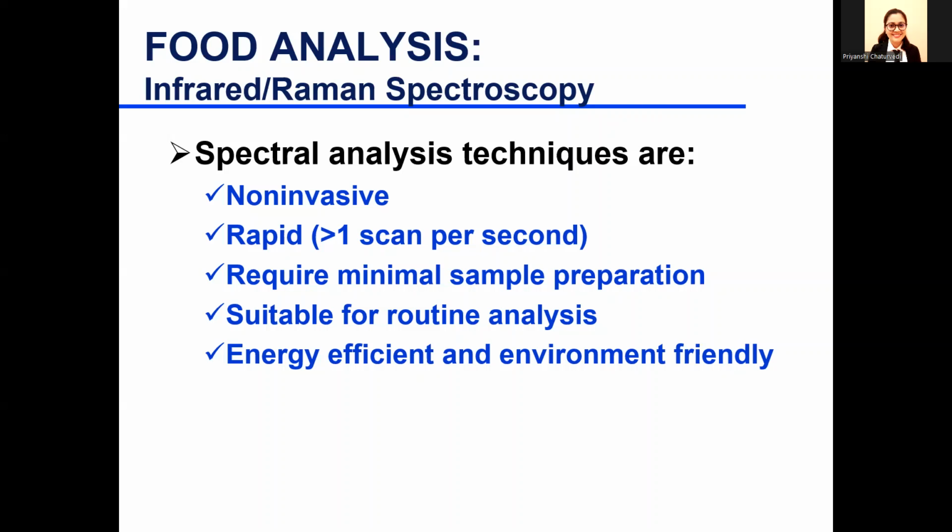But if you do that, you have to make sure that you regularly calibrate and check the calibration on your spectrometer. So you'll always want to be doing routine test analysis in between, just a test to make sure that your primary method agrees with your secondary method.